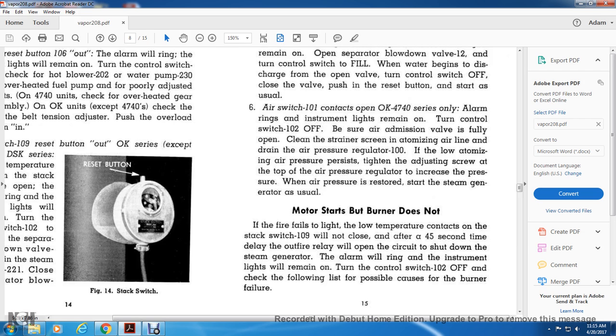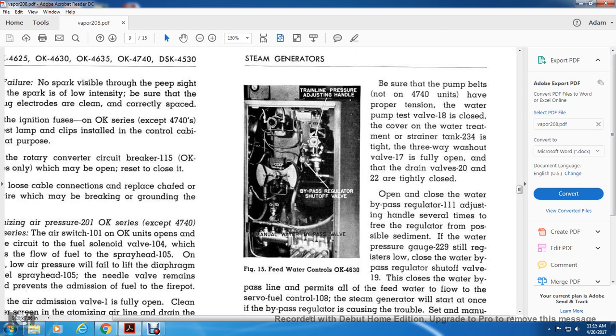Check the following list for the possible causes of the burner failure. 1. Ignition failure. No spark visible through the peep sight glass, or the spark is low intensity. Be sure that the spark plug electrodes are cleaned and correctly spaced. Check the ignition fuse of the OK series except the 4740s, and use the test lamp clips installed in the control cabinet for the purpose. Check the rotary converter with the circuit breaker 115, OK 4740 series only, which may open with the reset to close. Tighten the loose cable connections related. Replace chafed or broken wire which may be breaking or grounding the circuit.